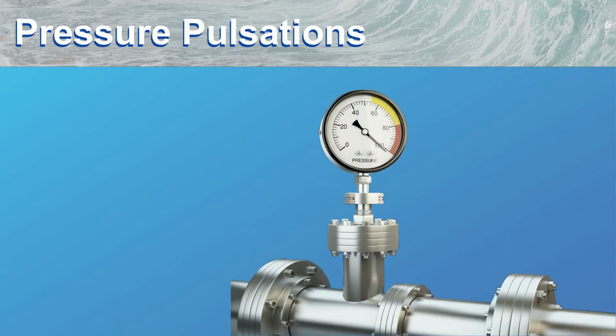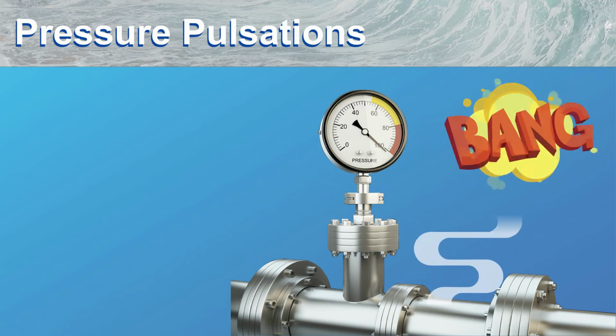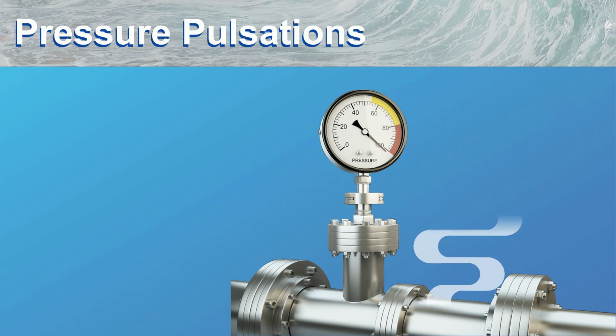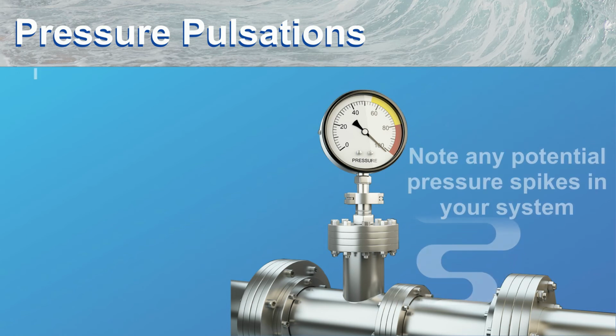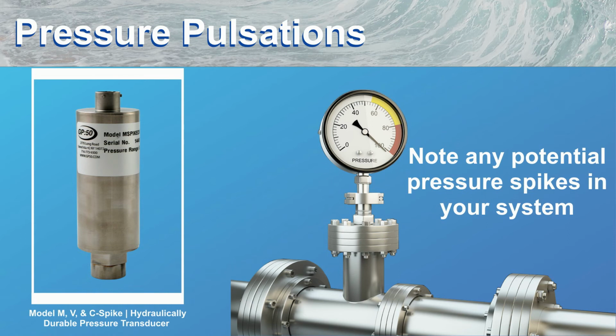Pressure spikes are very common in many hydraulic applications. Spikes due to a valve opening and closing or rapidly turning a pump on and off can send a pressure wave that can damage a transducer. Knowing that this is a potential issue when specifying a transducer allows us to provide a snubber to dampen the pulsations, or we can provide high-proof pressure to improve longevity.